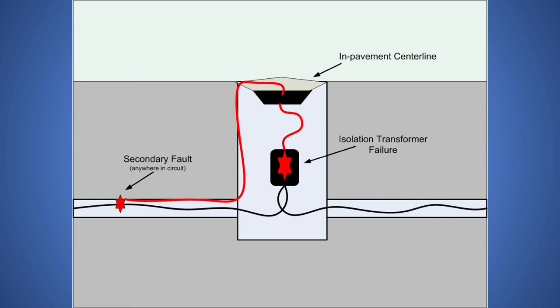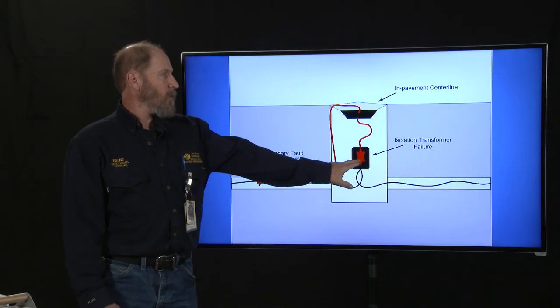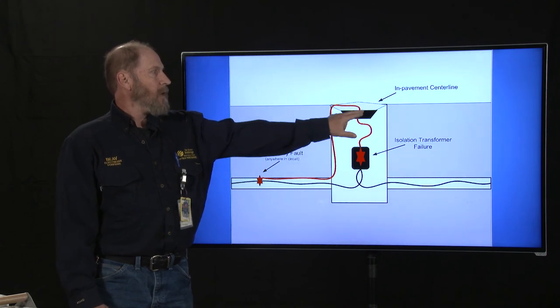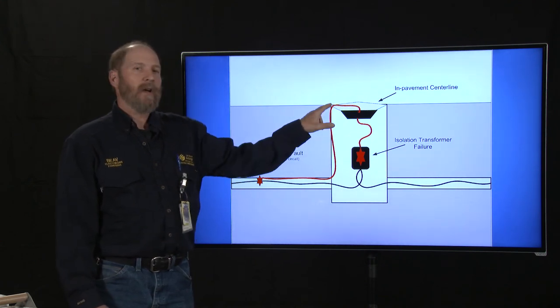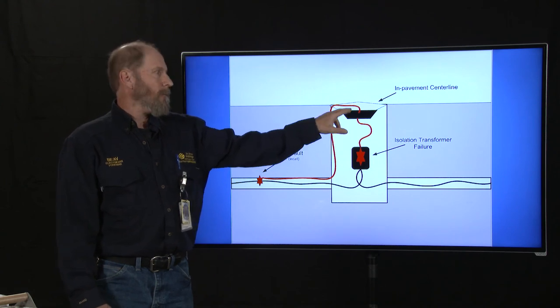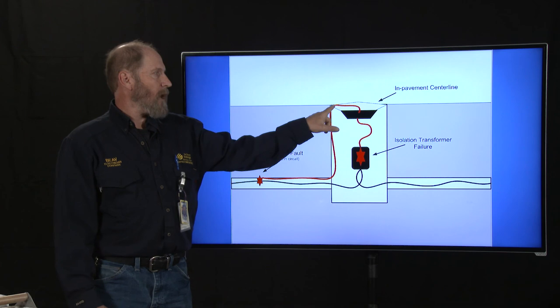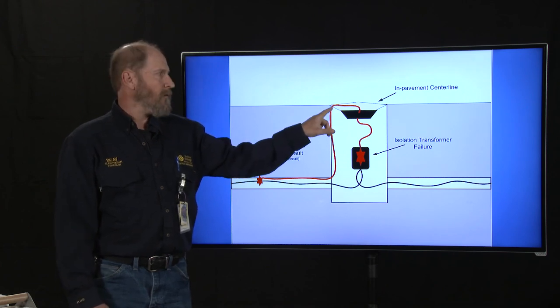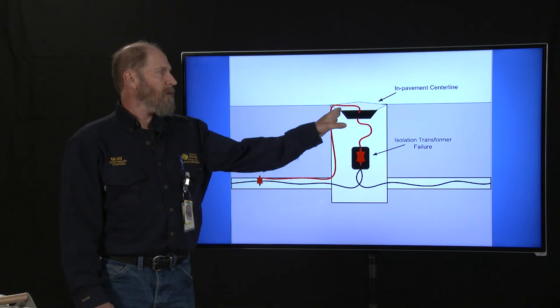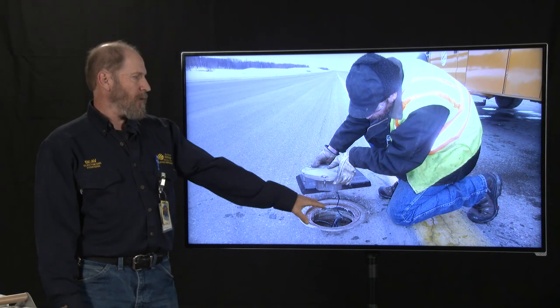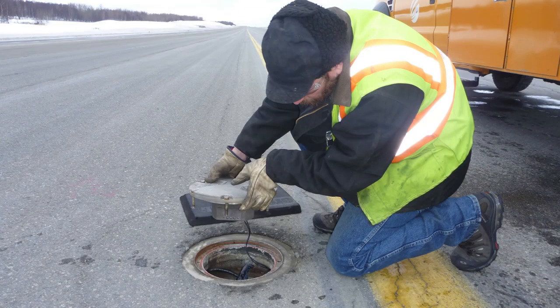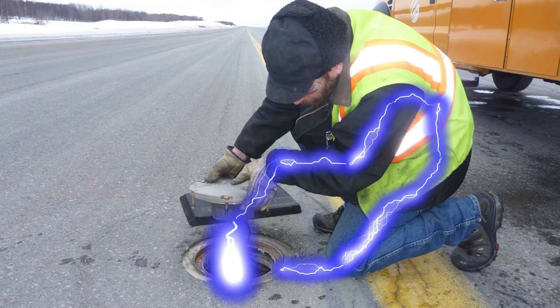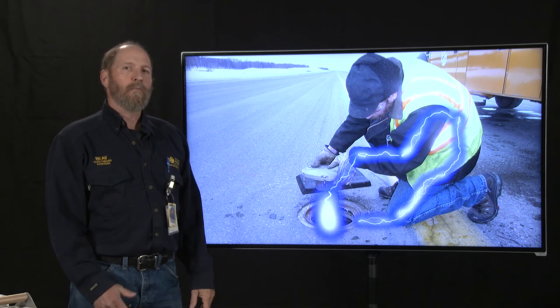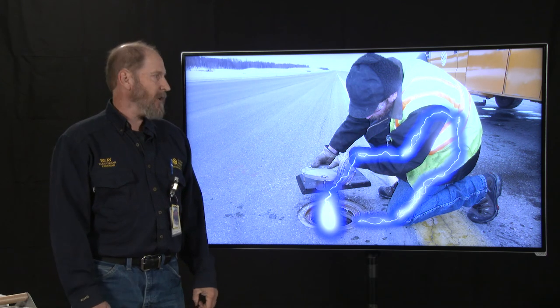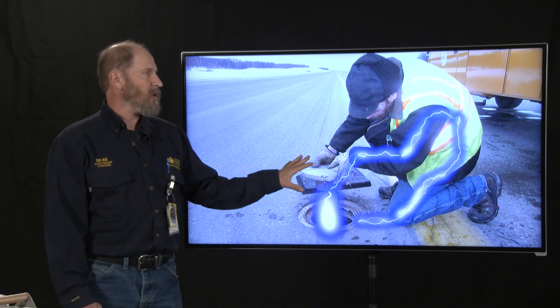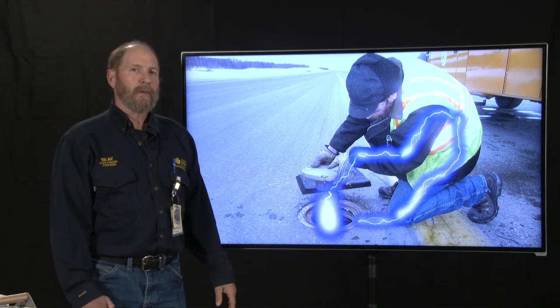Here's another situation that can happen with an isolation transformer fault going through a taxiway center line. The taxiway center line is a big hunk of aluminum. It can be carrying that current and you'll never know it. It wouldn't even warm up. But this is the spot right here. This transition right here is what we need to focus on. What happens if this fixture is lifted away? The electrician pulls it away, breaks it from its ground connection, and it's going to go through him. Electricians have been found dead with burns on their hands and burns on their knees. It's a very serious situation. If this happens to you, it will probably kill you.